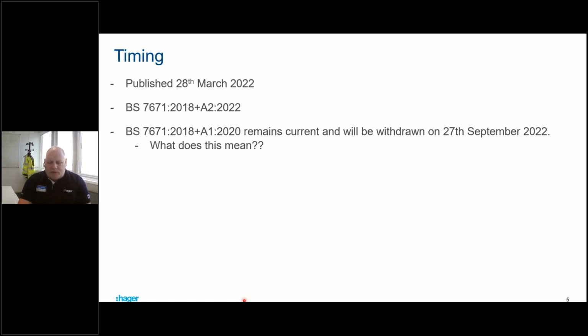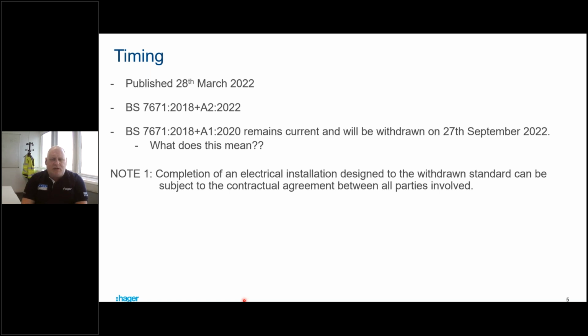Now, what does this mean for us? Okay, so if we've started an electrical installation before the 27th of September, what does that mean for us? We would have started that to Amendment 1. We are allowed to complete that installation to Amendment 1, as long as we've got everybody's agreement on that. So possibly building control, possibly the building owner, the main contractor. We've all got to sit down and say, yes, we are happy, we've started that, and we will complete it to Amendment 1. Anything started after the 28th of September must be to Amendment 2.